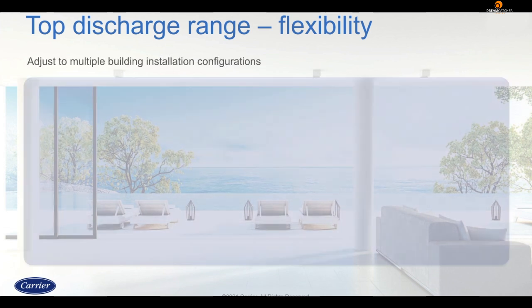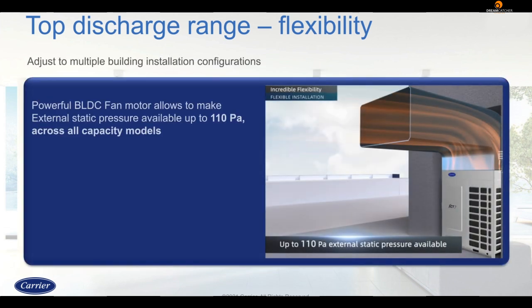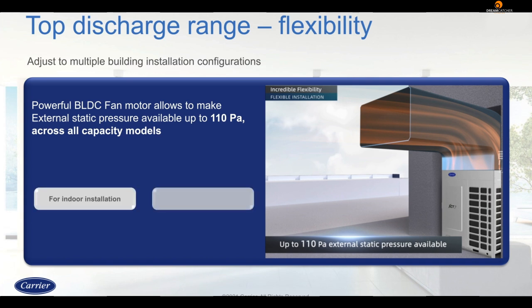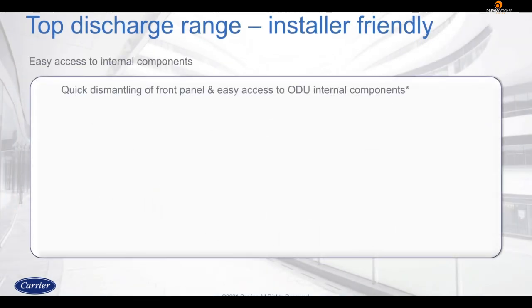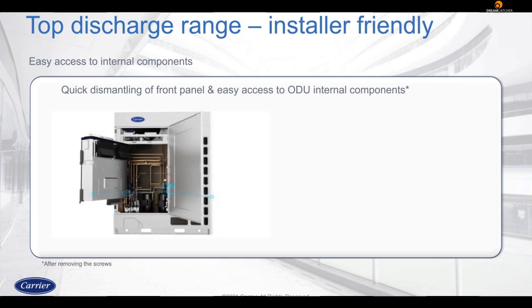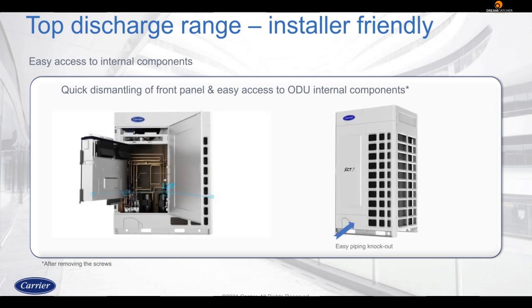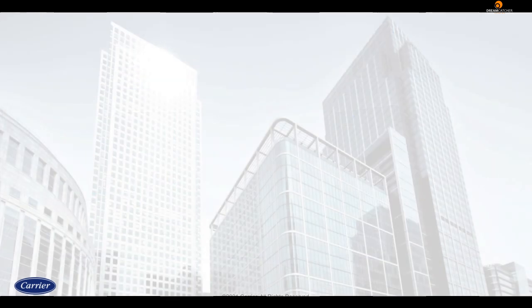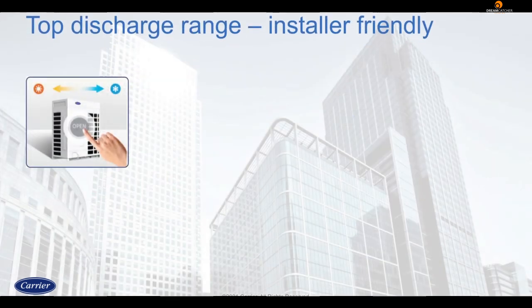The system can adjust to multiple building configurations, and the powerful BLDC fan motor ensures that an external static pressure of up to 110 Pa is available across all capacity models, even if it is installed at a poorly ventilated balcony or refuge story. And it is extremely easy to install as well. The front panel can be dismantled quickly and allows for easy access to the internal components of the ODU. Once the system has been fully commissioned, the installer can test it with the touch of just one button and does not have to switch each indoor unit on separately.